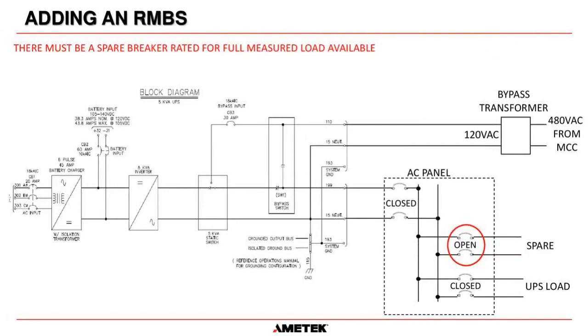Okay, then what we need to do is get your electrical department to install a spare breaker in the AC panel that is rated to carry that full load current that you just measured. So we said 20 amps. Obviously, you're not going to put a 20 amp breaker in there. So I would say anything about 30 amps or above for a 5 kVA system would be adequate. Okay. So this is just the prep work that you need to do before you get going.